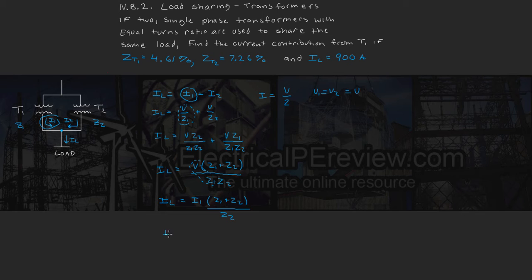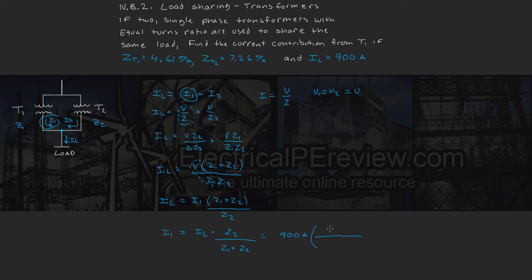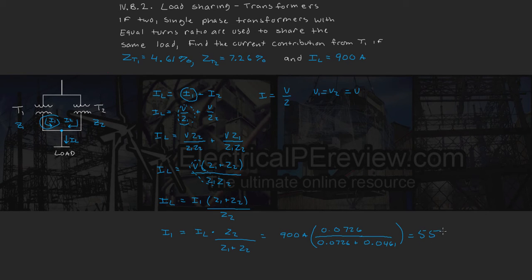Setting this equal to I1, we get I1 equals load current times Z2 over Z1 plus Z2. Plugging in our values: 900 amps times 0.0726, divided by 0.0726 plus 0.0461. Calculating this, we get I1 equals 550.46 amps — that is the current contribution from transformer 1.